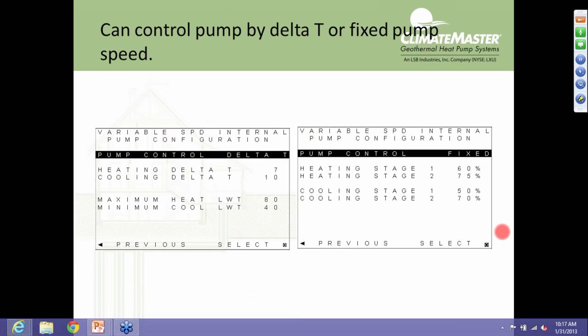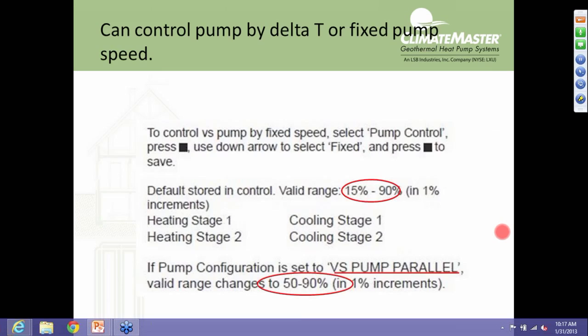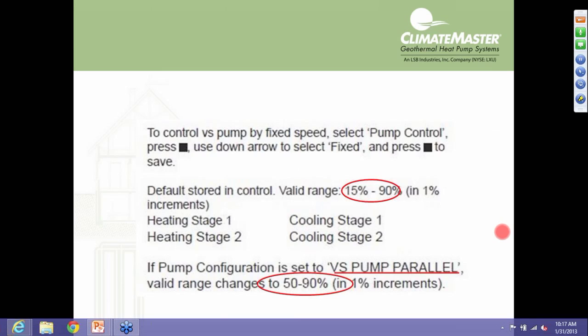Now, the pump range. If you choose, again, the default option, the variable speed pump in single, so meaning one unit, one loop, the range of the pump is 15% to 90%. So that's the range of the pump that we operate within. We don't go any lower than 15%. We don't go any higher than 90%. If we choose variable speed pumps in parallel, we minimize how low we let that pump go, and we only go down to 50%, so 50 to 90%. And we react much quicker to any change in what's occurring in the system. Again, because pumps in parallel, it's an arm wrestling match between our different units with their pumps.